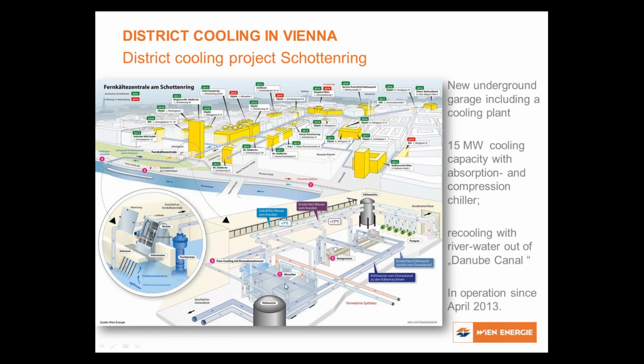And also we use it in terms of economics, because, as I showed on one of the first slides, we have this combination of a lot of cogeneration here in Austria. So if the electricity price is low, the heating price is high, and on the other side, if the electricity price is high, the heating price is low. So with this cooling plant, I always have one cheap technology and one expensive, and it might change within the year. With these two technologies I can do some hedging, so we can always use the more economic part, either the electrical chillers or the absorption chillers.